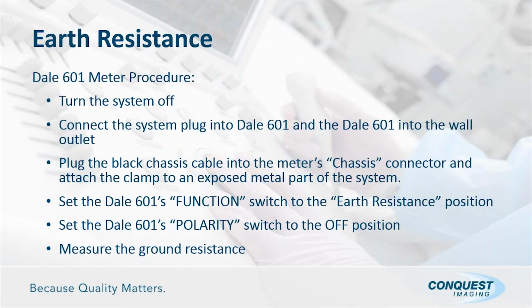And in order to do this, we turn the system off. We connect the system plug into the Dale 601, and the 601 into the wall outlet. When we do that, we want to confirm that, again, our wall outlet is correctly wired with the 2 green lights on the bottom. Once we're clear that we have a good circuit, plug the black chassis cable into the top of the meter and connect the clamp to the exposed metal part. Most of the time we use the grounding lug on the back.